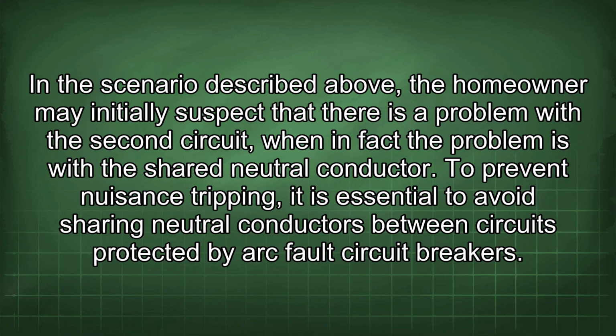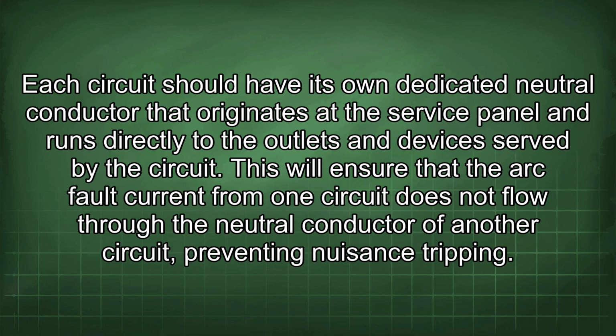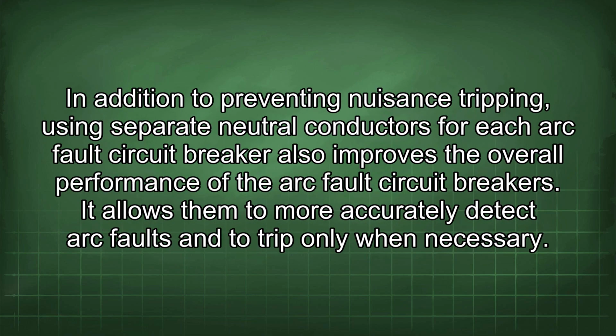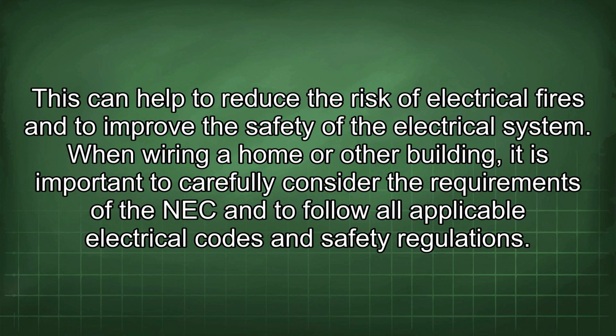To prevent nuisance tripping, it is essential to avoid sharing neutral conductors between circuits protected by arc fault circuit breakers. Each circuit should have its own dedicated neutral conductor that originates at the service panel and runs directly to the outlets and devices served by the circuit. This will ensure that the arc fault current from one circuit does not flow through the neutral conductor of another circuit, preventing nuisance tripping. In addition to preventing nuisance tripping, using separate neutral conductors for each arc fault circuit breaker also improves the overall performance of the arc fault circuit breakers. It allows them to more accurately detect arc faults and to trip only when necessary. This can help to reduce the risk of electrical fires and to improve the safety of the electrical system.